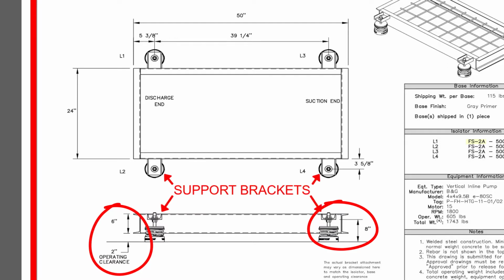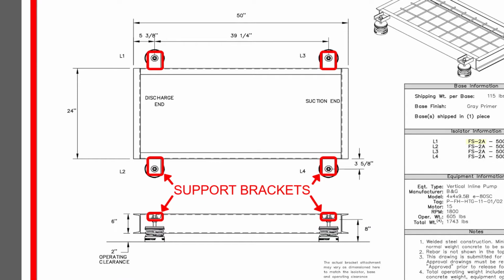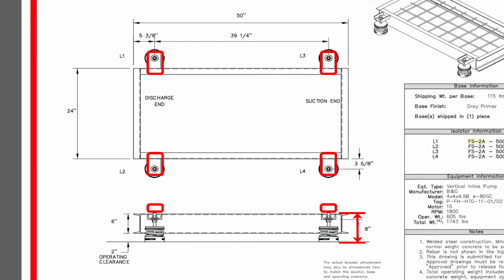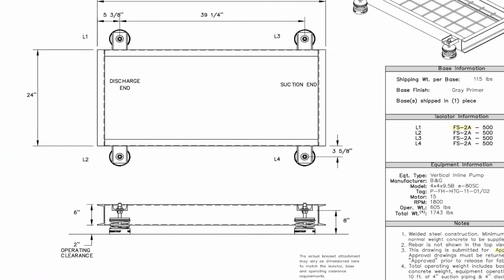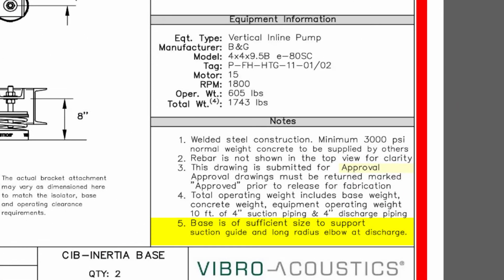This graphic is generic and doesn't show the actual bracket locations. In this case, since 6 inches plus 2 inches is 8 inches, and the operating height of the isolator is 8 inches, then the support brackets will be mounted on top of the frame instead of on the side as shown here. Inertia bases for most pumps should be sized to support the first elbows on both the inlet and outlet connections. We'll see that in the site walkthrough.